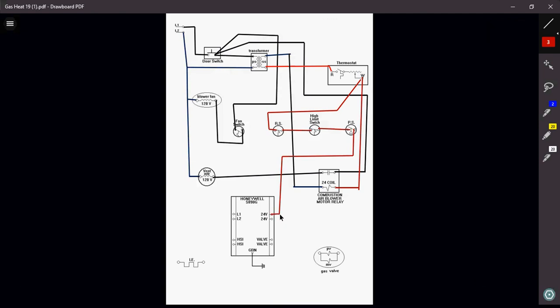Okay? So now in the event of anything that happens with this furnace, if any one of those switches happens to open, vent motor happens to fail, the pressure switch is going to open. If I have a high temperature problem, gets too hot, high limit's going to pop. If I have a rollout, that's going to pop. If any one of those switches happens to open, I'm going to kill the 24 volt circuit down at my ignition module. And when that happens, I'm going to kill my ignition sequence. Okay? In this case, it's going to be the gas valve. Depending on the ignition module itself, that 24 volt circuit can kill the entire thing. It's all different models out there that will do different things. But I'm killing my ignition source, my gas.